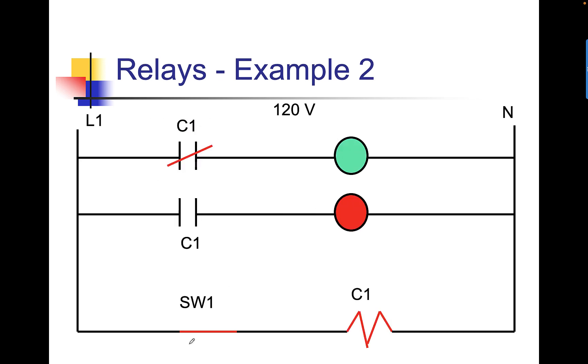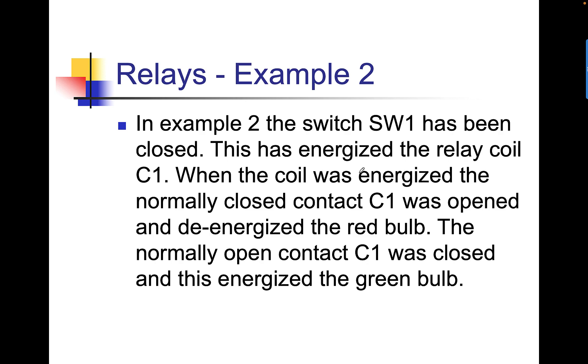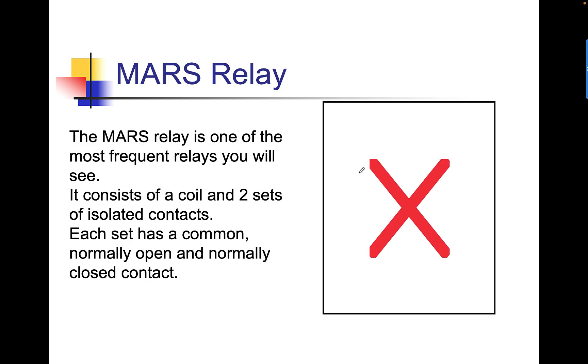Now, we close the switch. We now have closed the switch. C1 coil is now energized. What it did was close the normally open, the top one now has a slash, so it's closed, and it opened the bottom one. Our red bulb is de-energized, and our green bulb is energized. Switch 1 has been closed. This has energized the relay coil C1. When the coil was energized, the normally closed contact C1 was opened, and it de-energized the red bulb. The normally open contact C1 is closed, and this energized the green bulb.